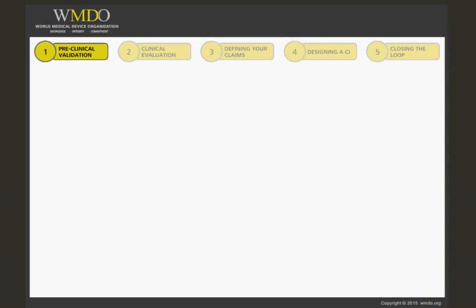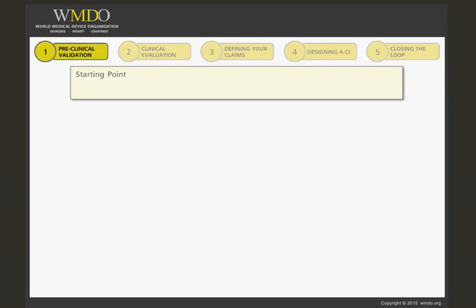In setting up your preclinical validation plan, you need to take into account the following criteria. First, your starting point is the risk analysis as well as the review of the essential requirements which devices need to comply with. Europe has a list of all the essential requirements a device needs to comply with, which can be used as a checklist.